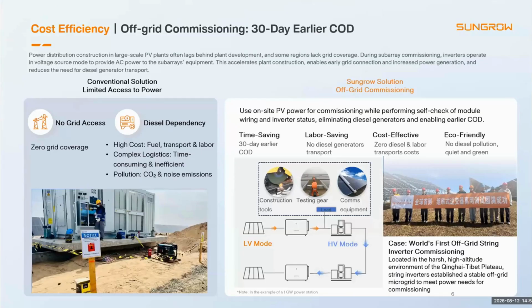Large PV projects often face a simple problem. The plant is ready for commissioning, but permanent auxiliary power is not yet available. And traditionally, I think EPCs rely on diesel generators. But with Sungrow's off-grid commissioning, the inverter can operate in voltage source mode and use PV power to support construction tools, testing equipment, and communication systems. This reduces diesel use and the logistics as well, and helps achieve earlier commercial operation. For a 1 gigawatt project, the example shown here can support up to 30 days earlier commercial operation date.